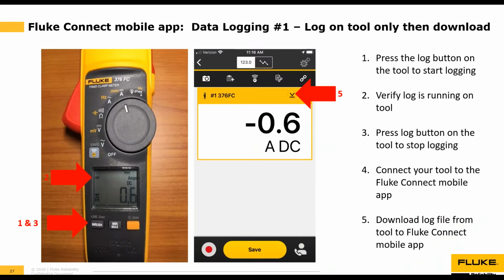So now that we've covered the three logging options, let's take a closer look at option number one and how we do that. So step number one is to press the log button. Now, in our case, the 376FC doesn't have a dedicated log button, but you'll see that it does have the word log above the inrush button. So if I press and hold the inrush button for 2 seconds, the log will start.